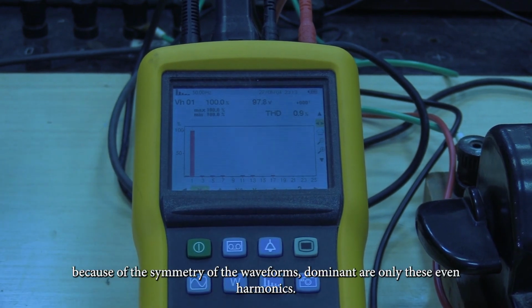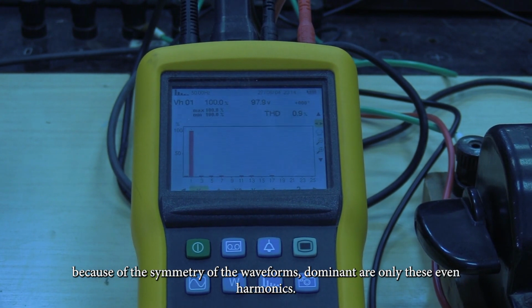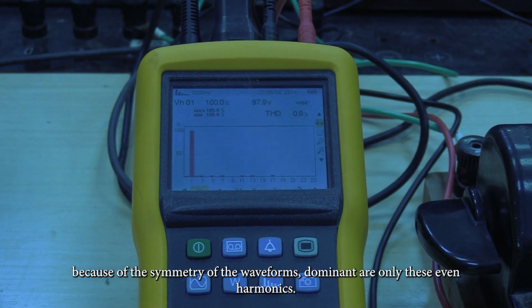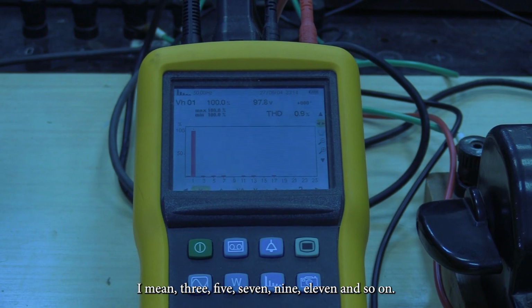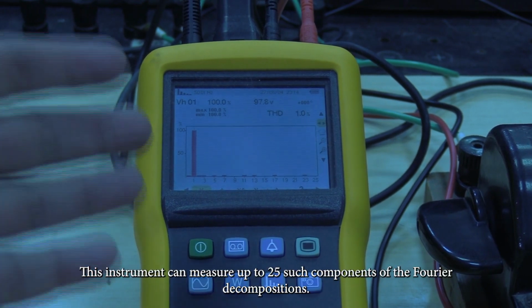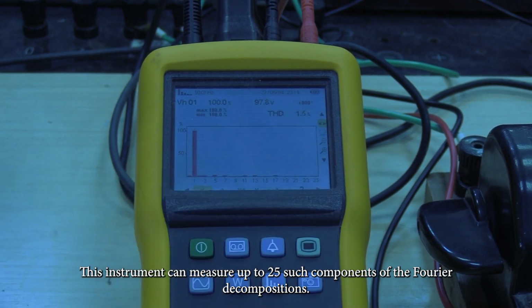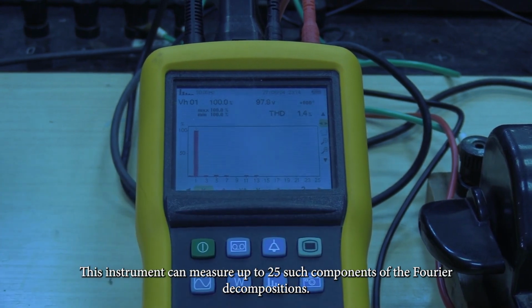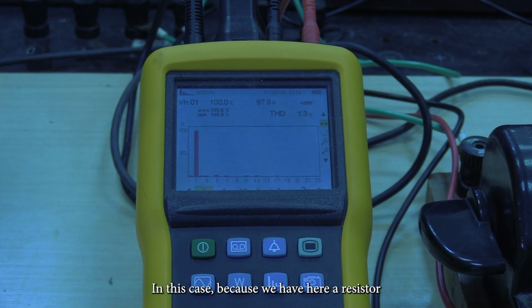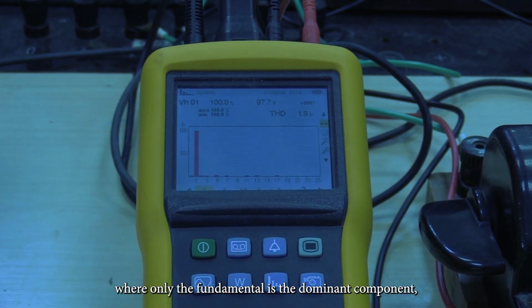Because of the symmetry of the waveforms, dominant are only the odd harmonics. I mean 3, 5, 7, 9, 11, and so on. This instrument can measure up to 25 such components of the Fourier decomposition. In this case, because we have a resistor, only the fundamental is the dominant component.